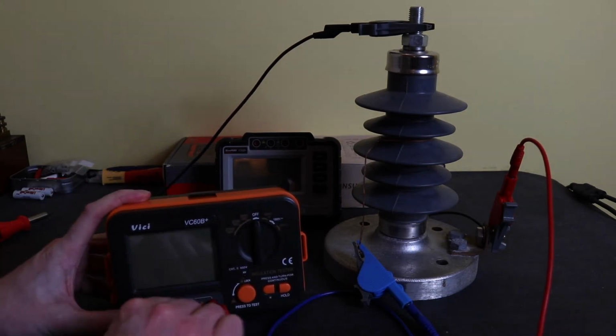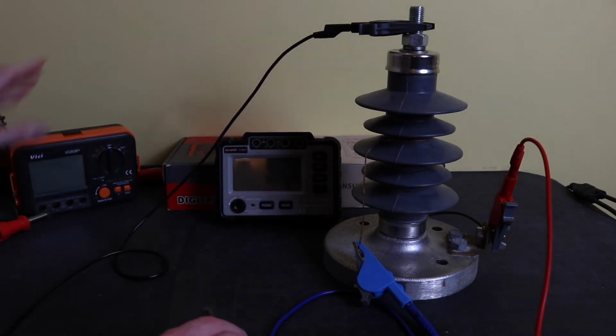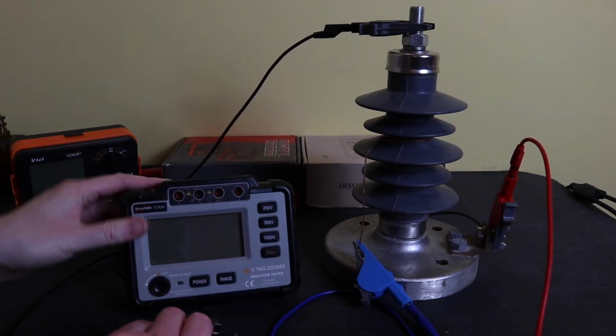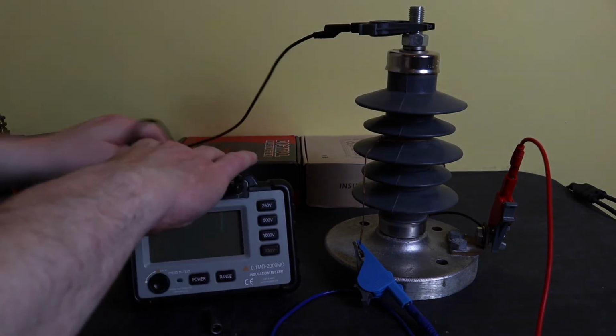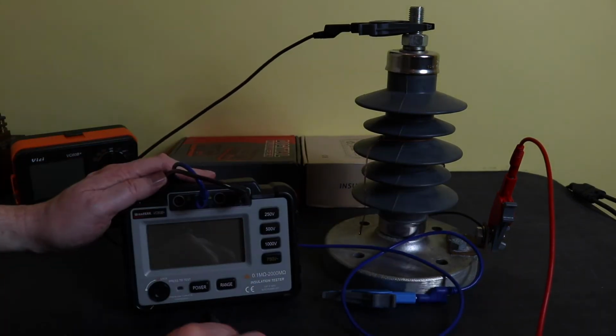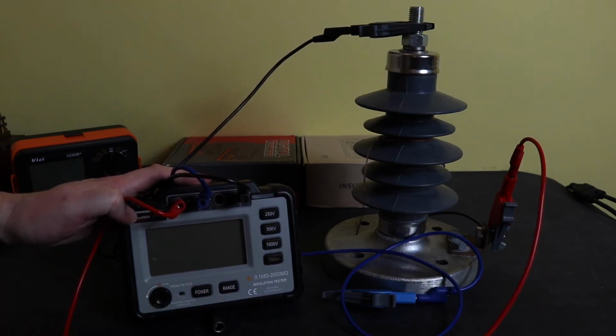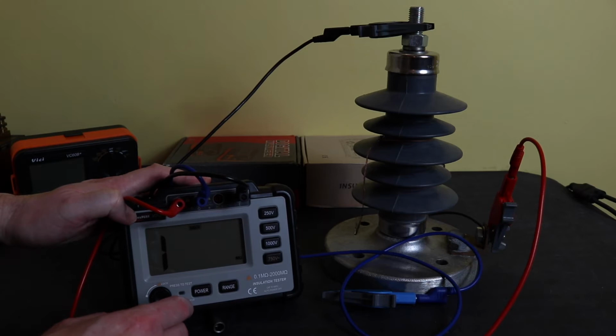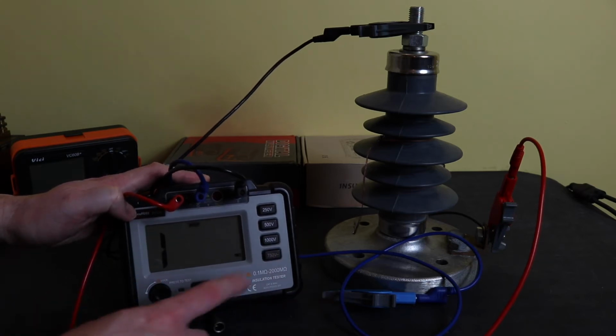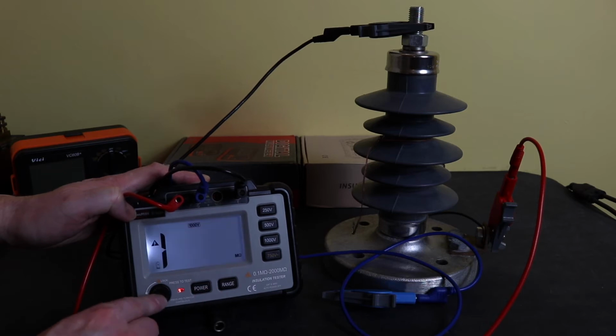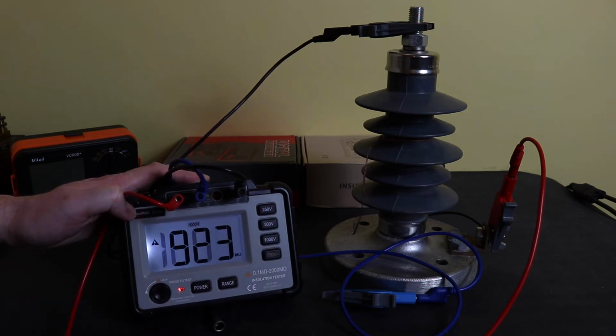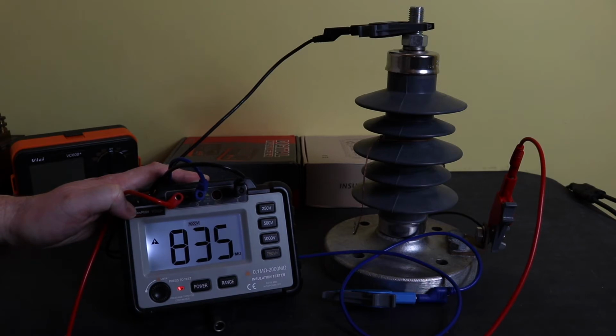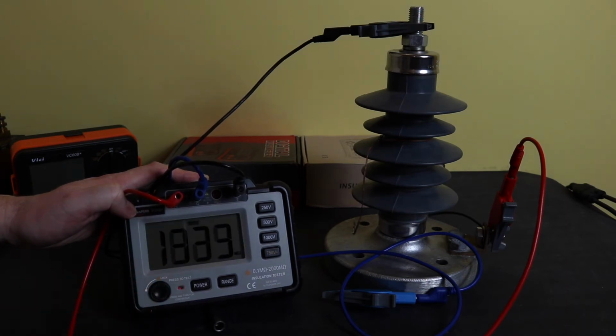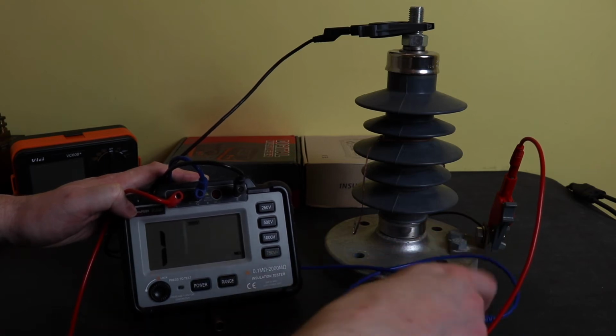Give the WinsPEAK unit a go. Try and keep the leads out of the way of the screen. So, power on. This is test without the guard terminal connected on 1000 volts. Press the lock, we should be around about 830-ish mega ohms again. 829, 828. That's pretty good. And then we'll connect up the guard terminal.